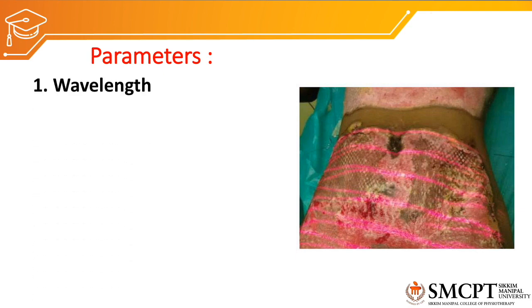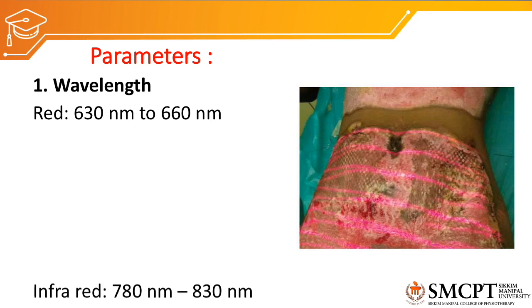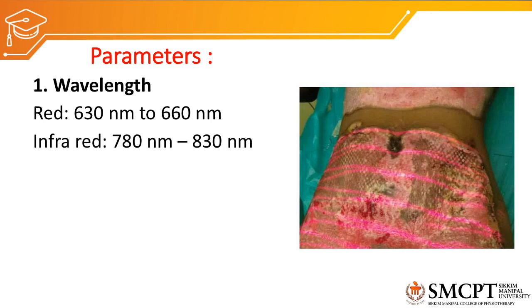The first parameter is wavelength. We have two types of laser based on wavelength: red visible light laser, ranging from 630 to 660 nanometers, and infrared laser, ranging from 780 to 830 nanometers. Depending upon the depth of the injury or wound, we select the type of laser. Red visible light penetrates approximately 1 centimeter depth, and infrared laser penetrates deeper, approximately 5 centimeters.